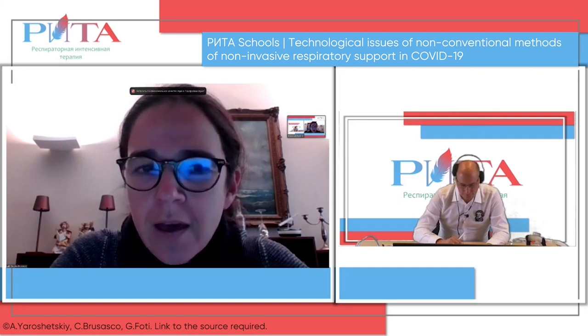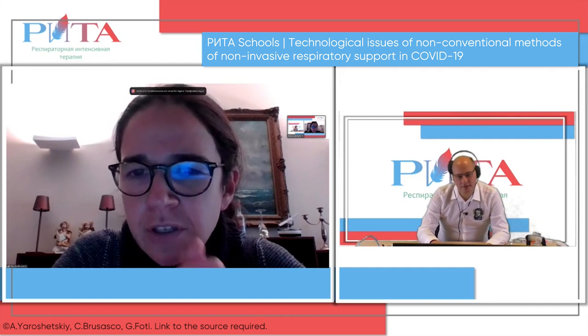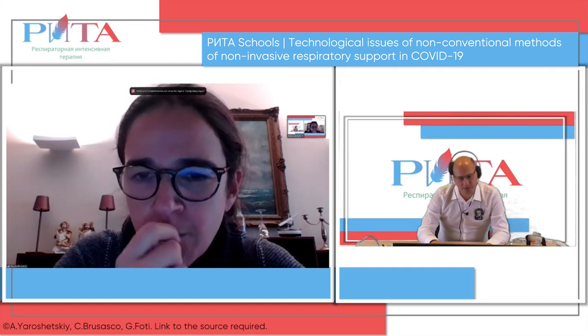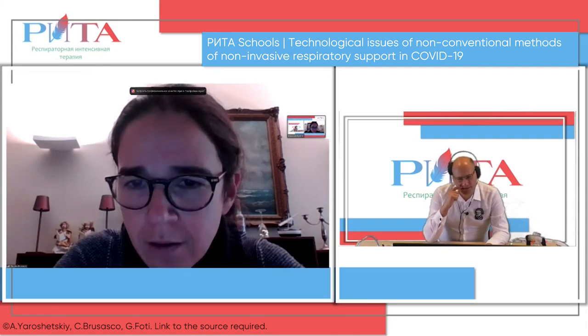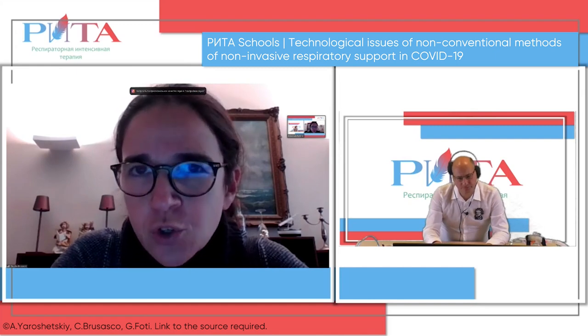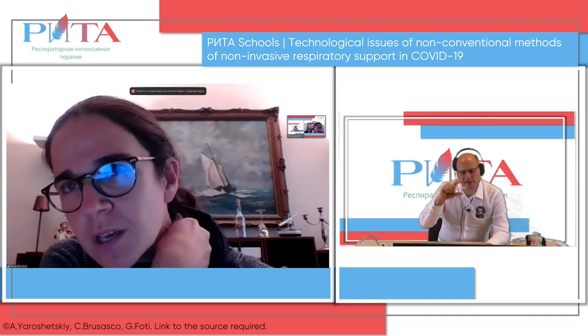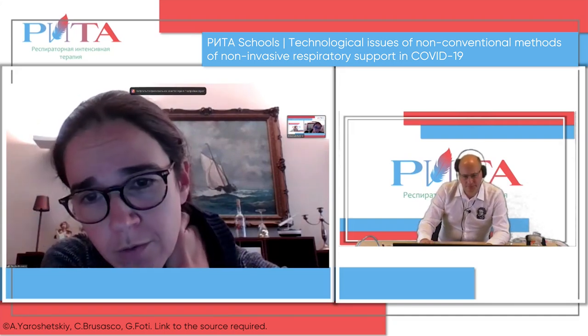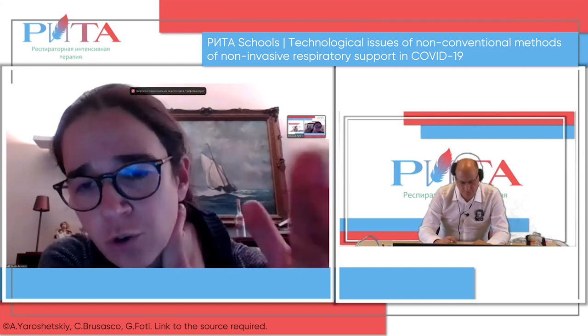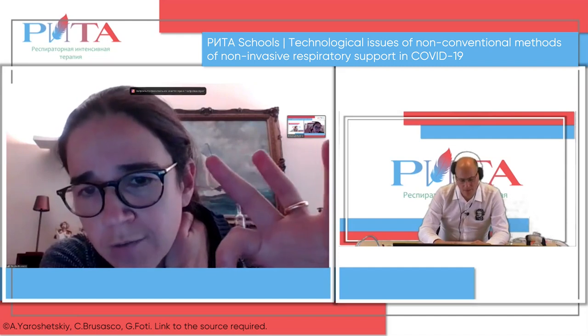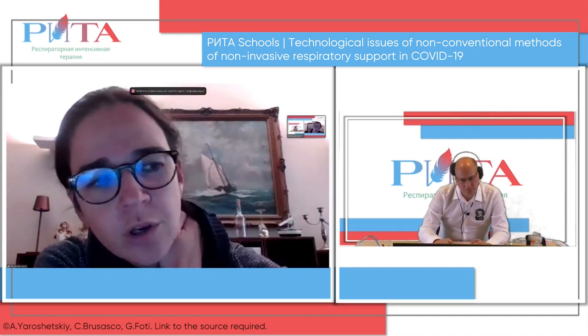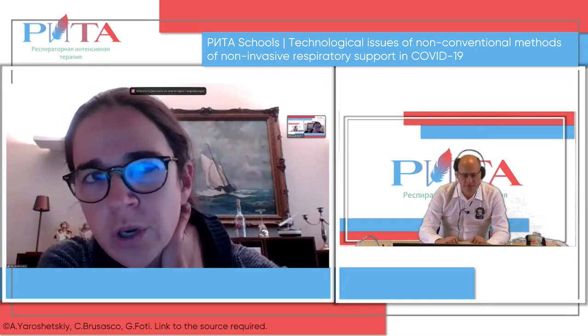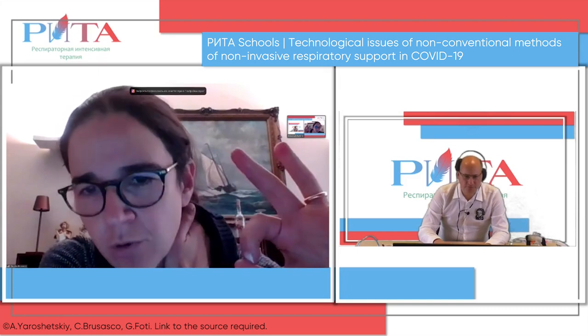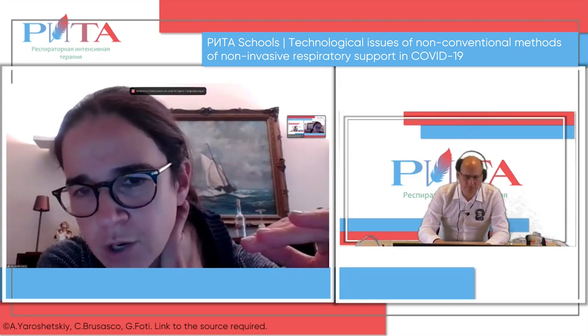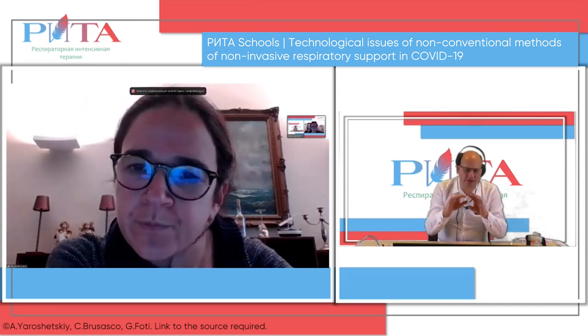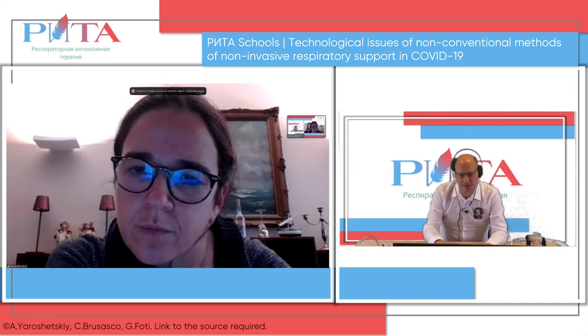With a little EPAP, a positive pressure at the mouth of the patient, but the patient's breathing always has to overcome that positive pressure. So it's very small expiratory pressure. Very small, and the patient is connected with ambient air through the Boussignac valve, so it's not at all a continuous positive airway pressure - during the breath, the patient always goes back to zero, to ambient air pressure. So it's old technology, not very well fitted for COVID patients, yes?